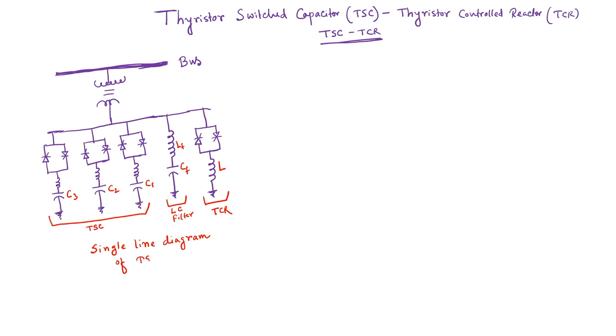As you know, this is the step down transformer, which we keep so that the voltage level of the TSC-TCR is much lower than the system voltage level. The system voltage can be a transmission line voltage level; in India it is 220 kV, 400 kV and 765 kV, which are pretty high. If we design this kind of static VAR compensator at such voltage levels, the compensator cost would be very high. So since it is a shunt connected device, we can step down the voltage level to a much lower level and design the static VAR compensator there.